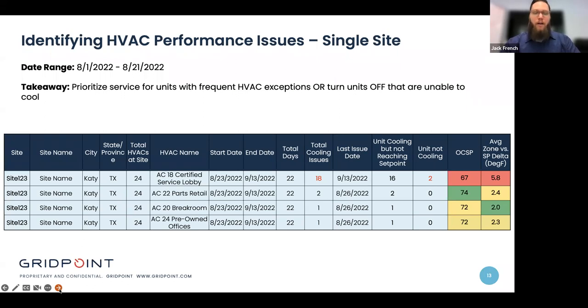So this particular operator was an auto dealership. And we see the top one for AC18 certified service lobby. Over this 22-day reporting period, it had 18 total cooling issues. So that's 18 in red. And then we go two columns over to the right, which says unit cooling, but not reaching set point. So of those 18 exceptions, 16 days, the unit was cooling, but it wasn't reaching set point. So that's that sort of priority 3 level exception. But on two of those days out of 22, the unit was not cooling at all. So it wasn't providing adequate supply temperature to the space to properly condition the zone.